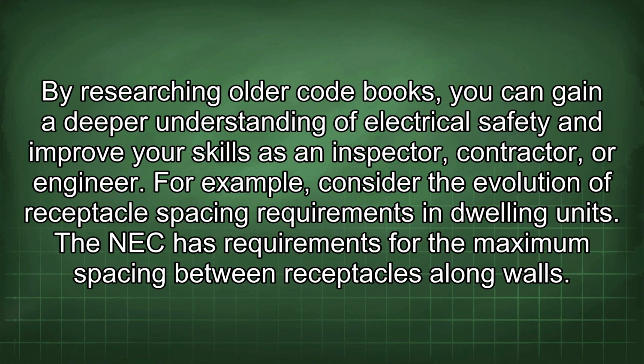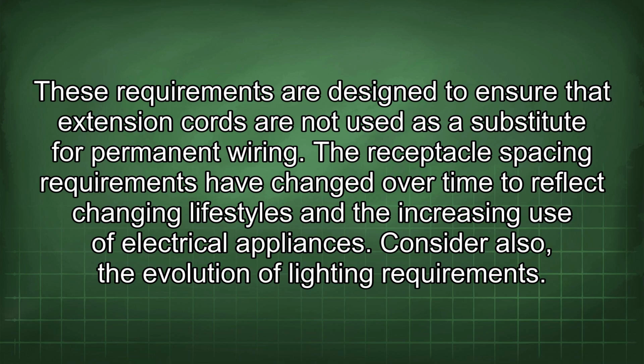The NEC has requirements for the maximum spacing between receptacles along walls. These requirements are designed to ensure that extension cords are not used as a substitute for permanent wiring. The receptacle spacing requirements have changed over time to reflect changing lifestyles and the increasing use of electrical appliances.